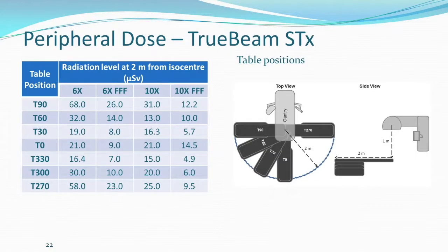The other interesting thing is the peripheral dose. We have been saying you removed one component from the LINAC which was contributing a lot of scatter. Now that component is not there, so naturally the scatter dose is less. So the peripheral dose should be less with the FFF beam. We did some measurements at 2 meter distance for various angles from the gantry, as you can see in this picture. You can see that for 6FFF, it is almost half that of 6X, and 10FFF also is less than half of 10X. It's all measured in microsievert, and you can see it is 68 and 26. So there is a significant reduction in the scattered dose when you use an FFF beam.